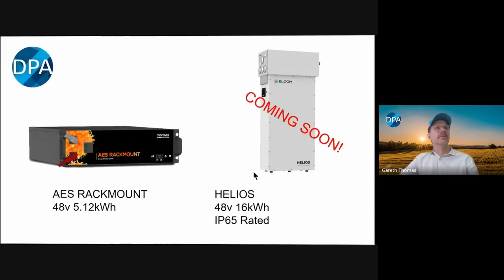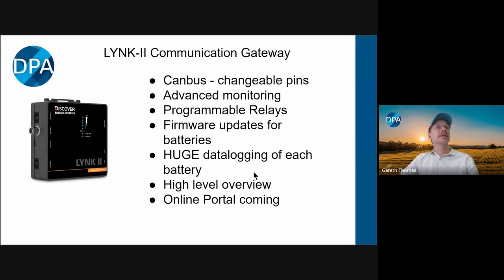So the Link 2 communication gateway - this is what's used to take all the data from the battery bank and put it all together. It then spits out whatever comms protocol you need for whichever inverter you're using. It's really adaptable - instead of just having a one-size-fits-all CAN bus output, it actually has a tailor-made CAN bus output for each inverter.